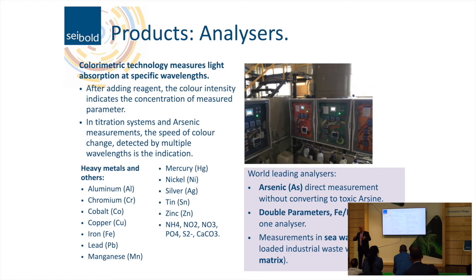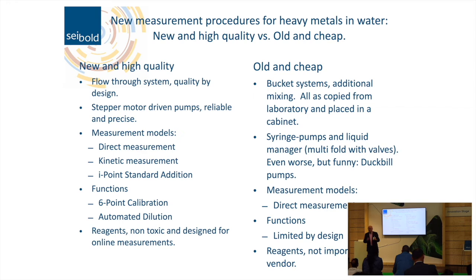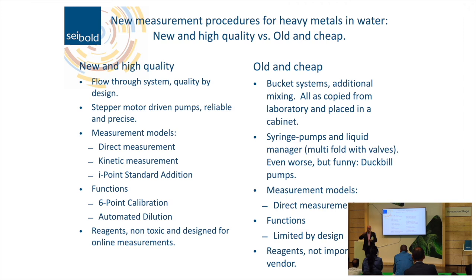How does our analyzer design compare to competitors? The most important feature is the flow-through design. Flow-through means every liquid is pumped by a dedicated high-precision peristaltic stepper motor pump, so you do not need any other appliances to get the mixed solution into the photometer. Competitors use different setups — a bucket system where you drop solutions into a flask and mix them — requiring a more complicated setup. Some use syringe pumps, which are cheap but a nightmare for maintenance.